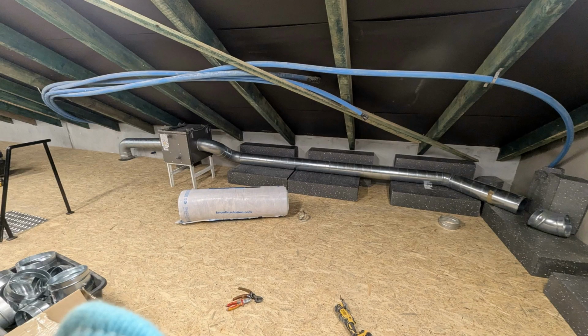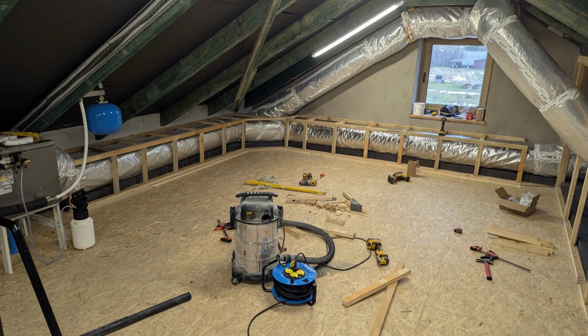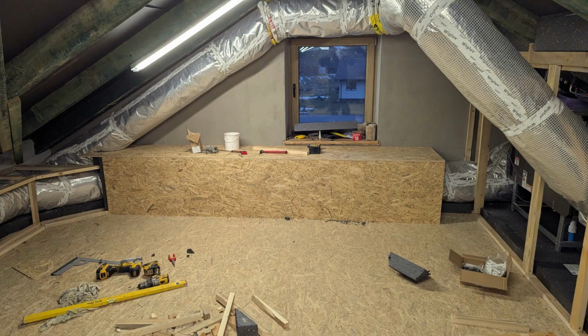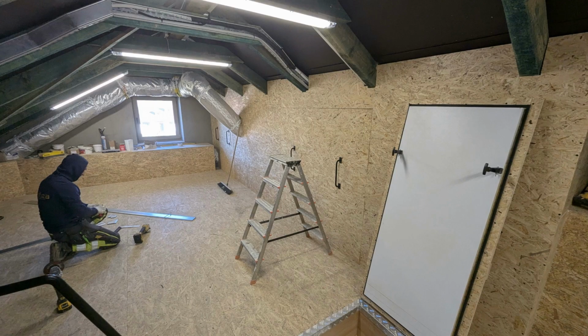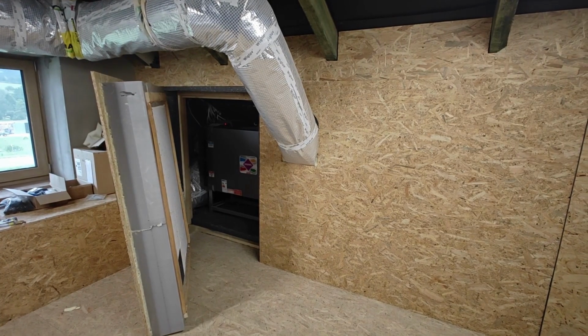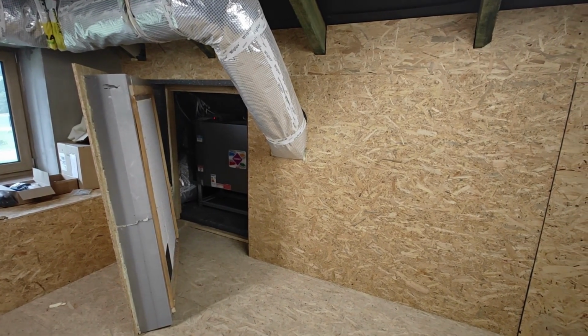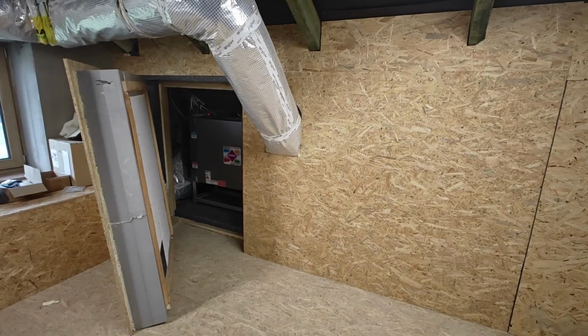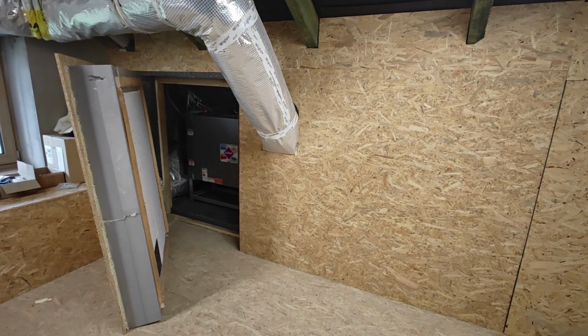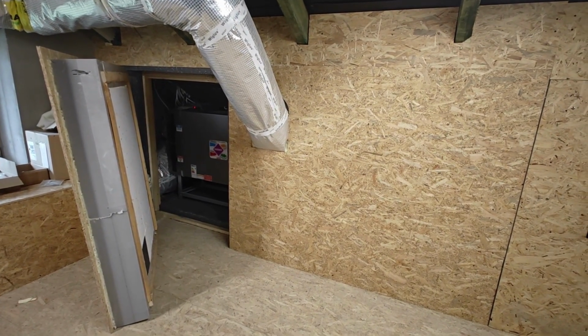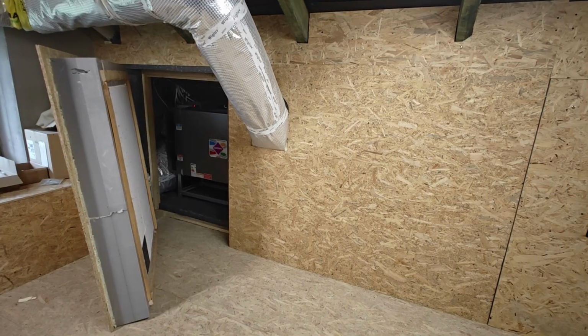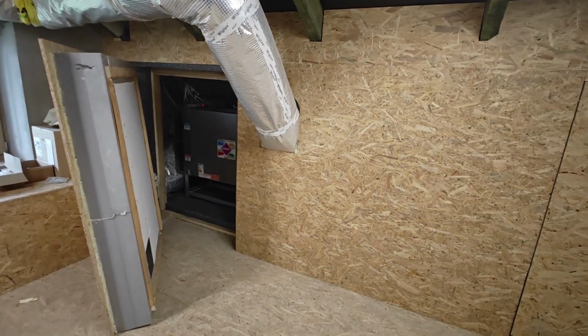This is a very critical spot that usually, especially in an uninsulated attic, poses a significant risk of moisture condensation that will have nowhere to drain. As I managed to install all the other vent pipes with proper slopes, I decided on very serious insulation here, as I checked this section several times with a thermal camera and didn't notice any water. The igloo itself also performs its function quite well. It is true that it's also insulated from the ceiling, and I personally think it shouldn't have to be. However, when the air conditioning provides heating in winter, due to minor leaks in the system, the temperature inside the igloo is usually above 10 degrees Celsius.